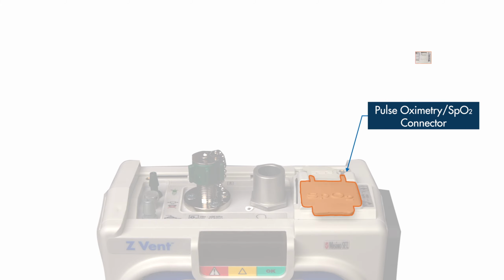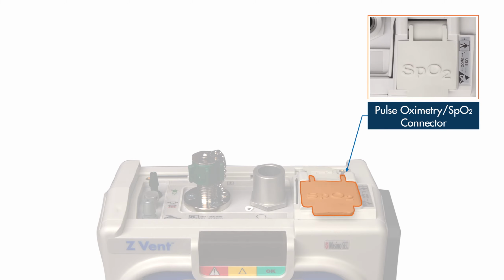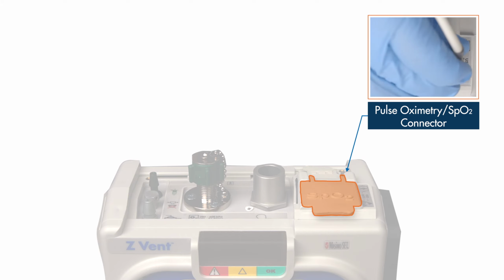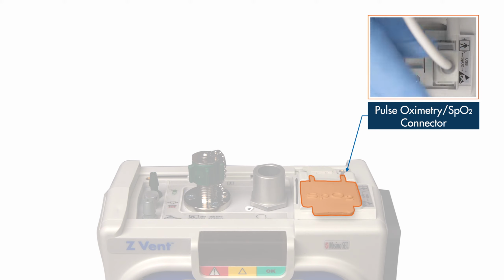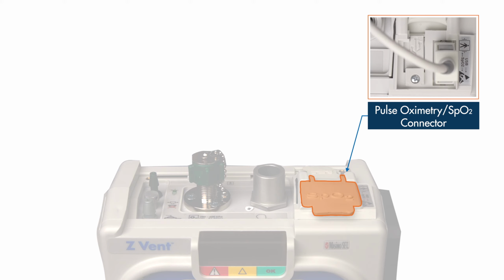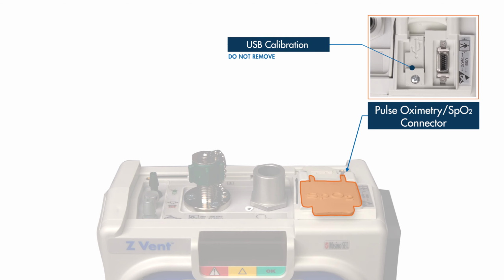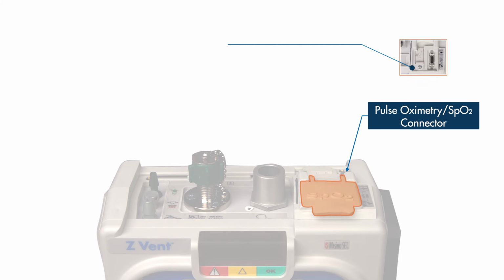At the bottom right corner is the pulse oximetry connector, under the square rubber cap labeled SpO2. The Masimo LNCS series of probes are approved for use with the Z Vent. When the appropriate sensor is connected, the pulse oximeter provides continuous, non-invasive monitoring of SpO2 and heart rate for adult, pediatric, and infant patients. Note that the USB port under the screw cap is used only when servicing and calibrating the device and should not be removed by the user.